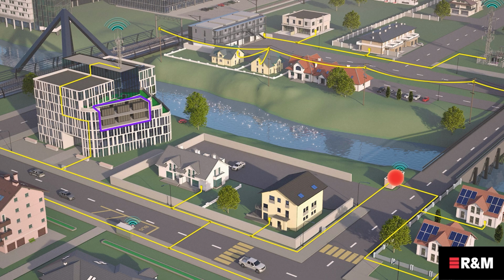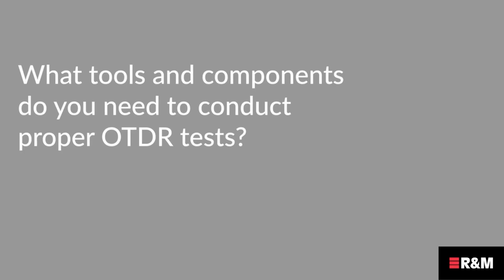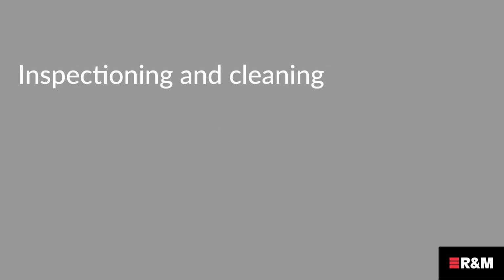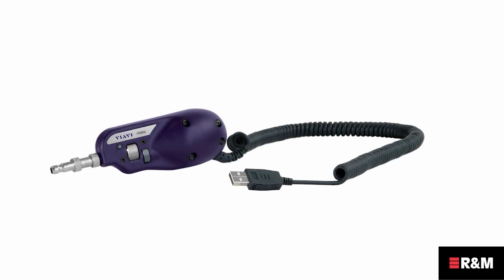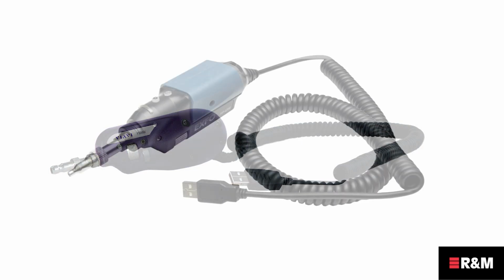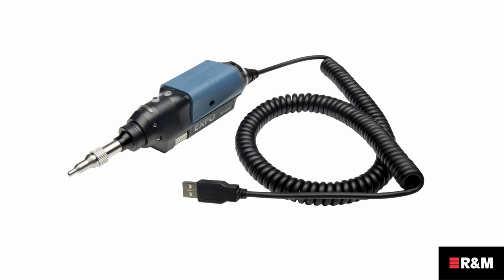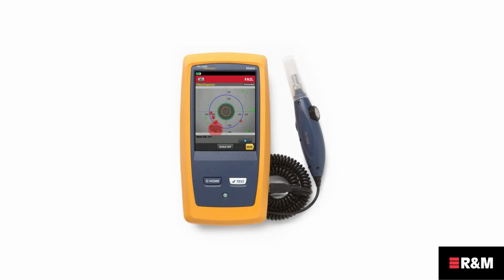locations. First of all, let's talk about the necessary tools and components needed in order to be able to conduct a proper OTDR test. Firstly, the condition and quality of the reference cords must be verified by inspection. In order to check the connector quality of the test reference cords, a microscope must be used. There are different kinds of microscopes on the market. We at R&M strongly recommend the use of video probes. These are 100% safe and can even be used to check the connector quality of active fibers.